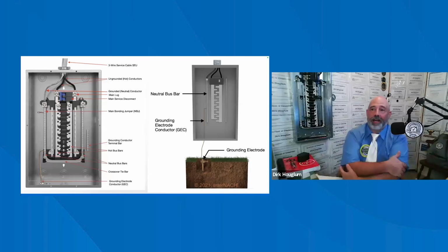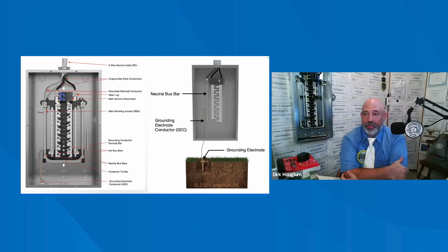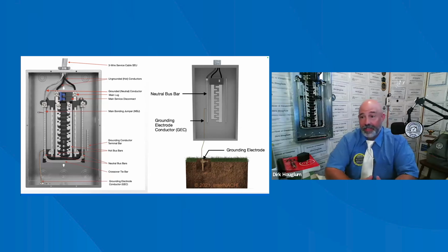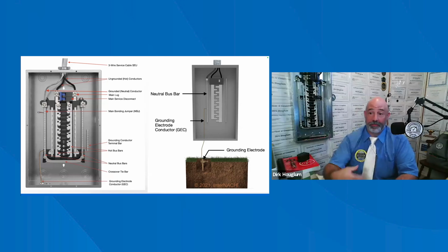If there's a ground fault in the house, the MBJ ensures the current can be safely directed to the ground, away from the house and the people inside. The MBJ provides a low impedance fault current path back to the power supply to facilitate the tripping of the overcurrent device in case of a ground fault. Grounding is the single most important component of a building's electrical system, and the MBJ is the single most important connection in the entire electrical system.